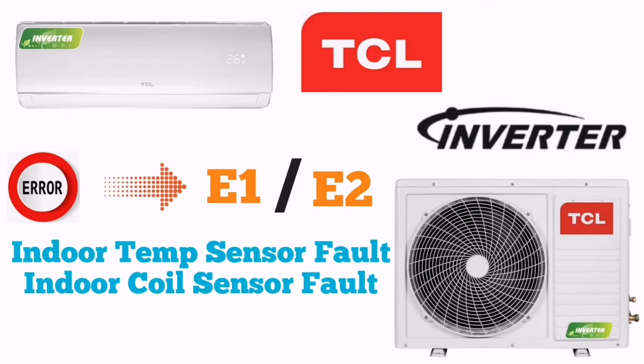And again, if you see the error, then you have to check the resistance of both sensors. If the resistance of both sensors is not 5 kilo ohms, it means the sensor is faulty. Then you have to replace the sensor and your unit will be in working condition, because when the resistance is not showing properly, it means the sensor has gone open or short circuit from inside. So we have to replace the sensor and the unit will be in working condition.